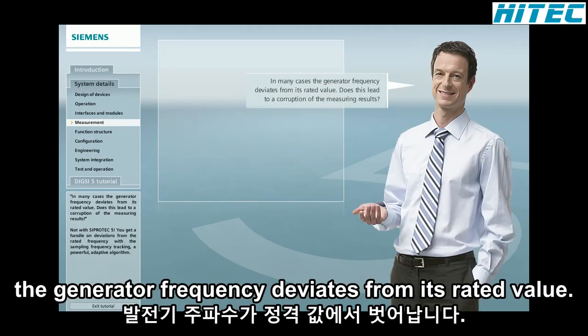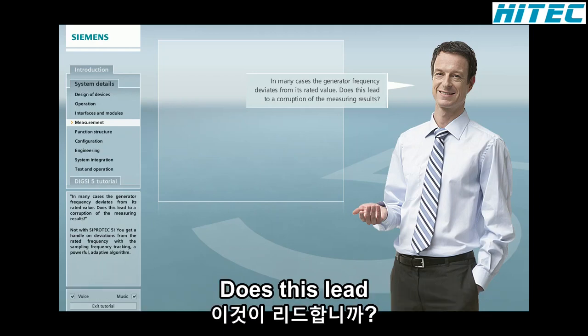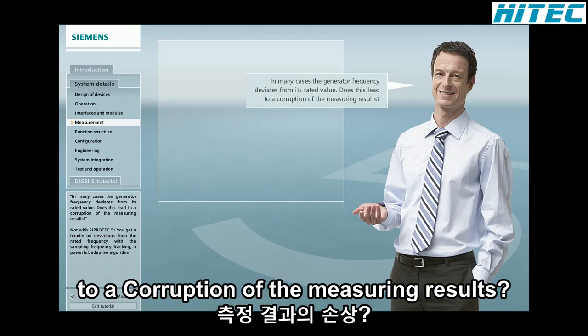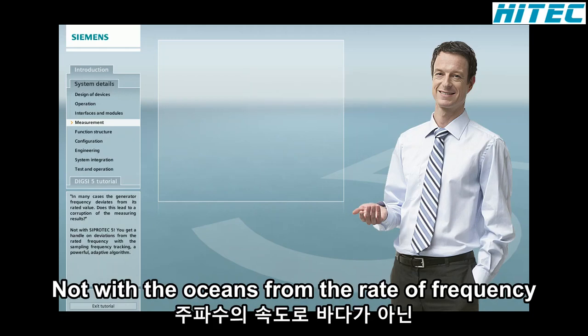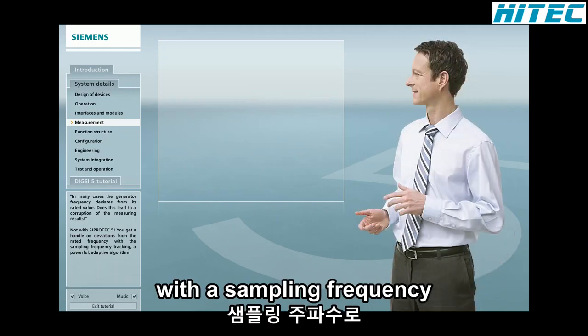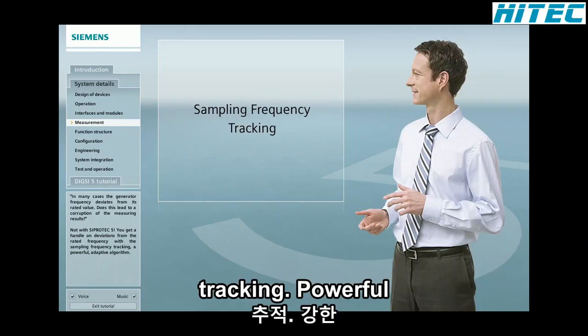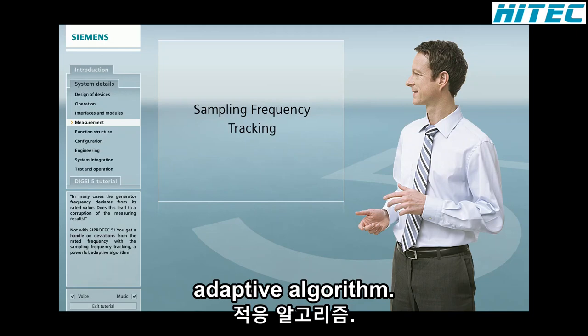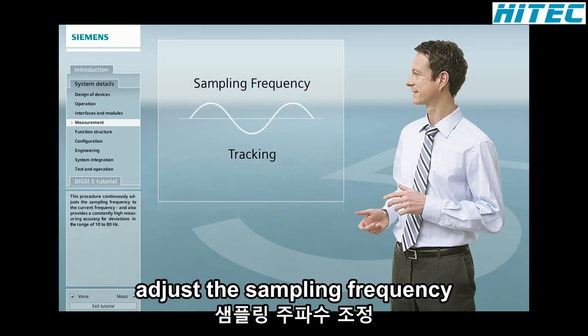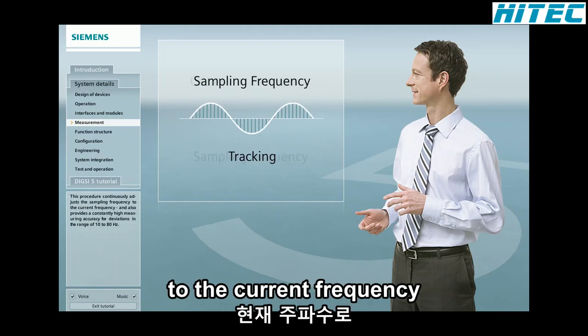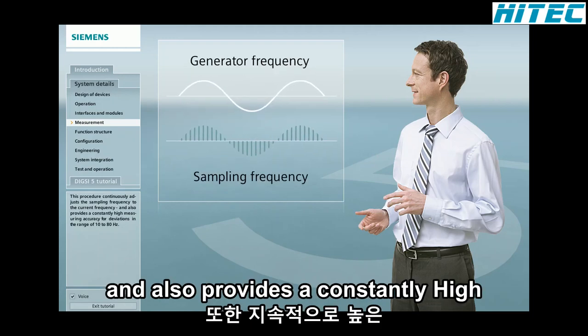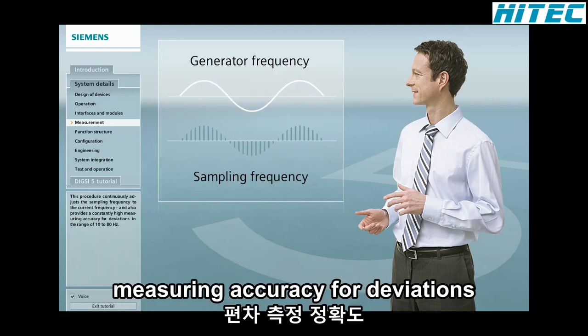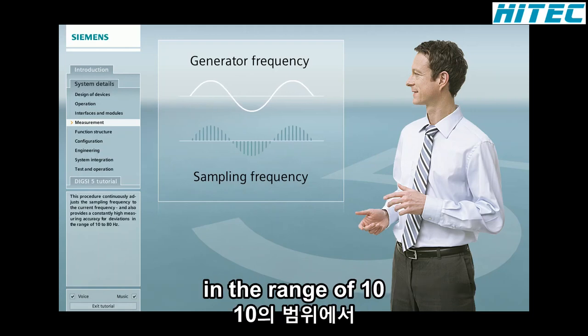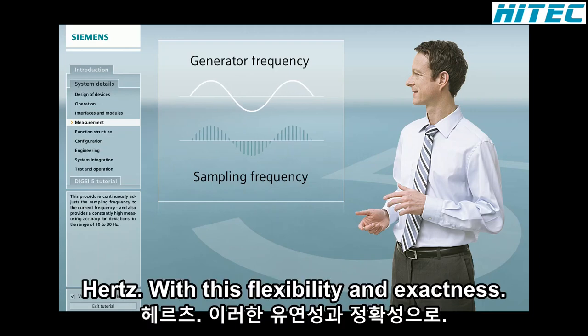In many cases, the generator frequency deviates from its rated value. Does this lead to a corruption of the measuring results? Not with SIPROTEC 5. You get a handle on deviations from the rated frequency with a sampling frequency tracking, a powerful adaptive algorithm. This procedure continuously adjusts the sampling frequency to the current frequency and also provides a constantly high measuring accuracy for deviations in the range of 10 to 80 Hz.